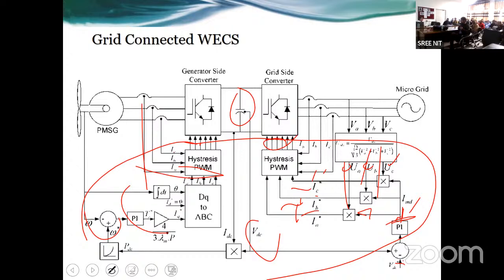Otherwise, you have to compensate for the delay. Compensating for the delay, deadband period. That is the period for which your system will remain uncontrolled. If you are putting in deadband intentionally, in some control applications some compensation comes, something like that. Some deadband calculation is also there due to practical problems. But during that deadband period, your system remains uncontrolled.